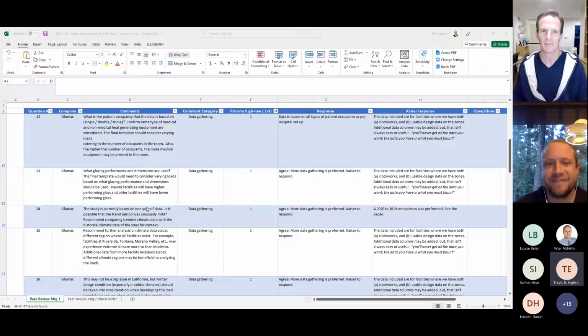So we had to go back. Someone actually went down to the site, looked at the BAS, got screenshots of every floor on the BAS, took those back, laid them over the design plans, and assigned the zone numbers back onto the plans. Then we dug the spreadsheets out of the design firm's files to look at the calculations behind all those zone calcs, and that's what we gave to the other team.